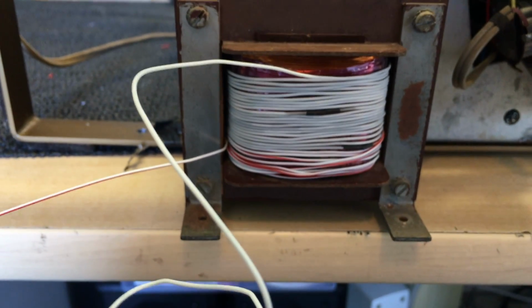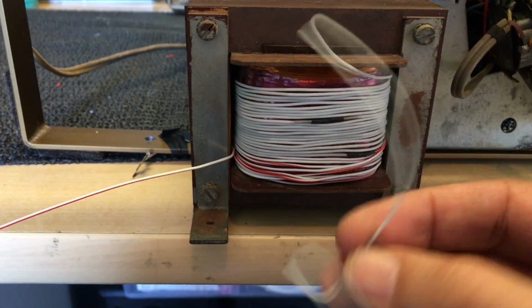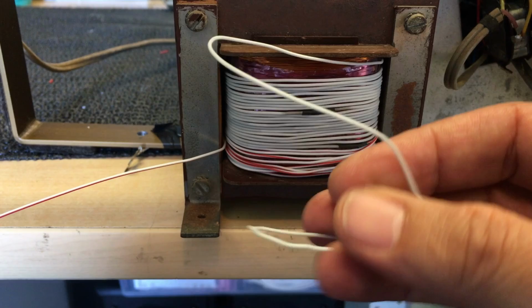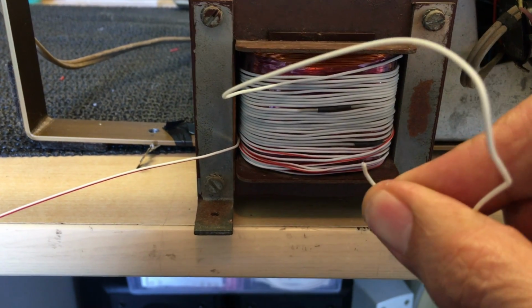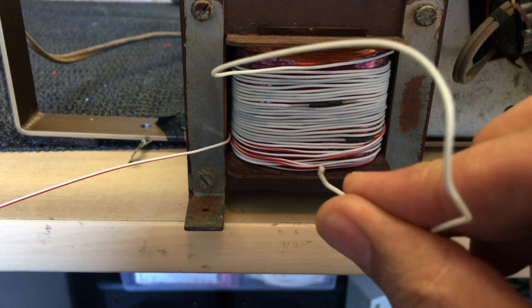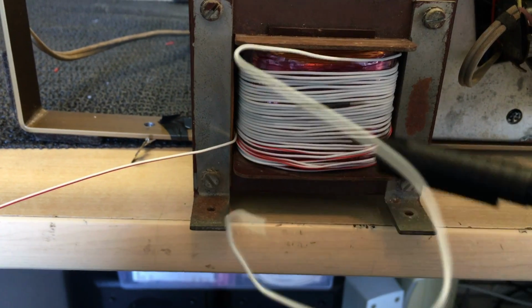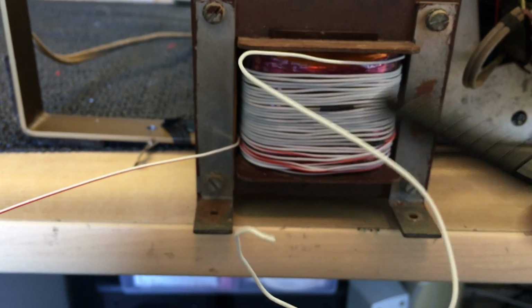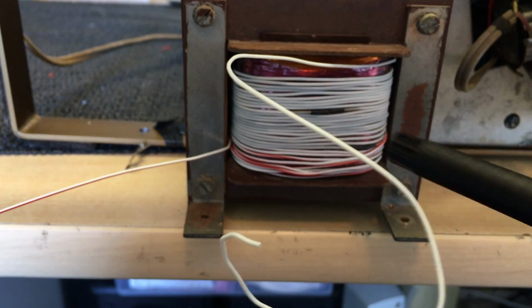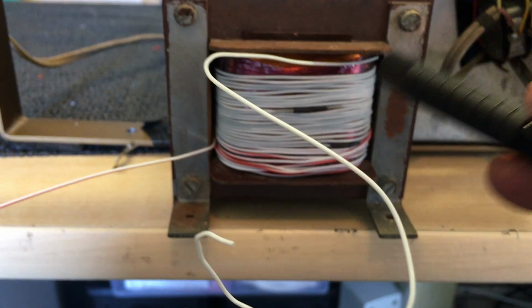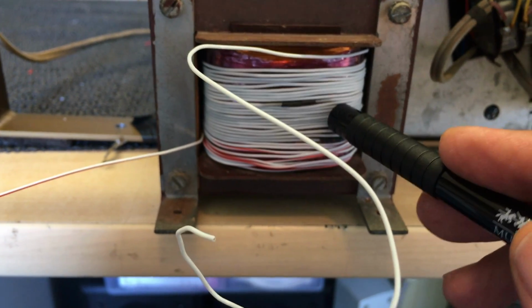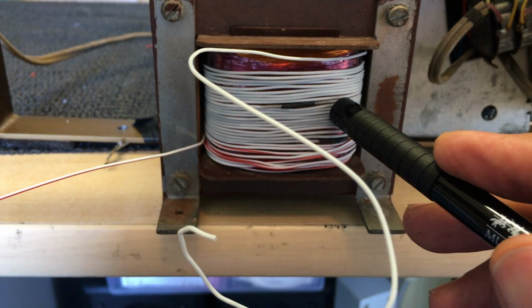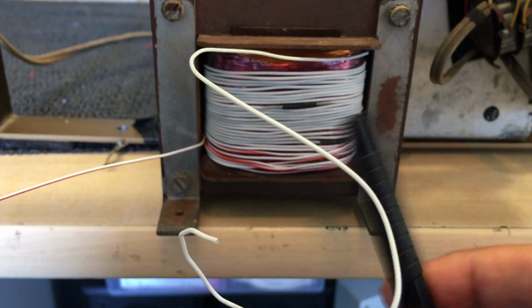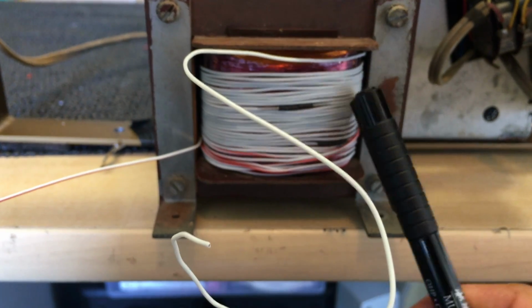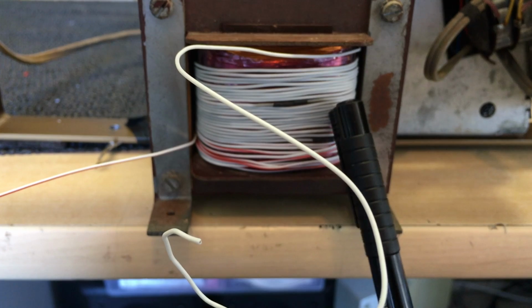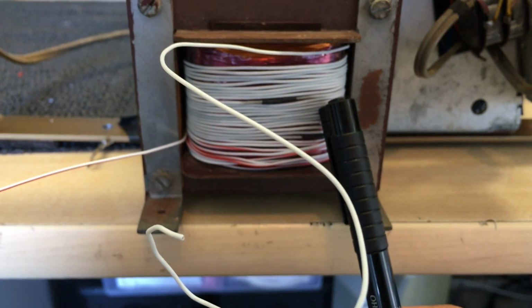Then what you do is take a normal piece of wire, any wire - this is solid core Cat5 wire that I just took out of a Cat5 cable. You wind, say, 3 or 4 coils around here, connect that to an AC voltmeter, and switch on your supply to see what voltage you get. In my case, with 4 windings, 4 turns, I got 1.2 volts. That tells me that with this particular transformer, I get 0.3 volts per turn.